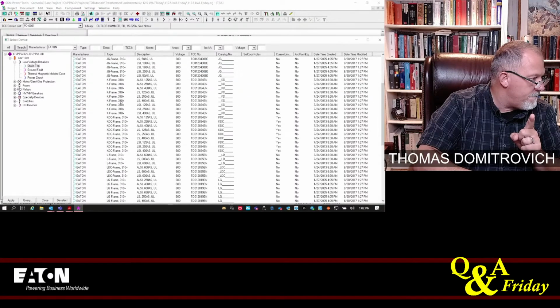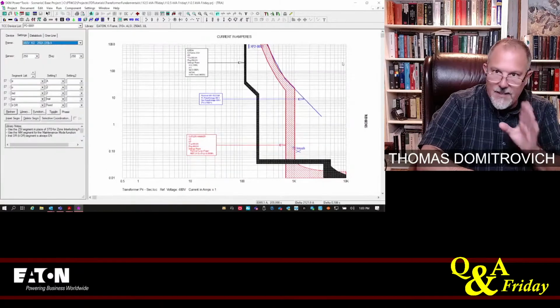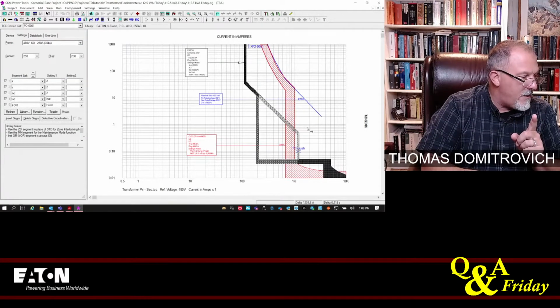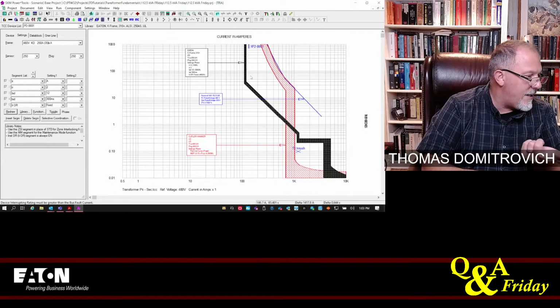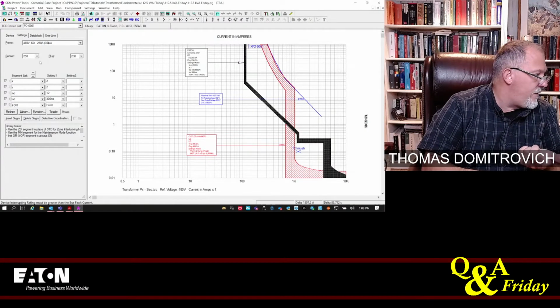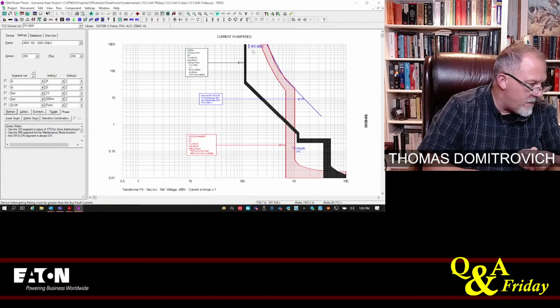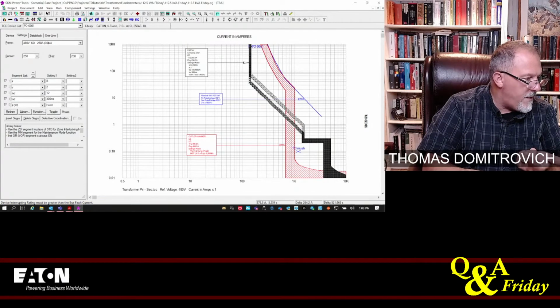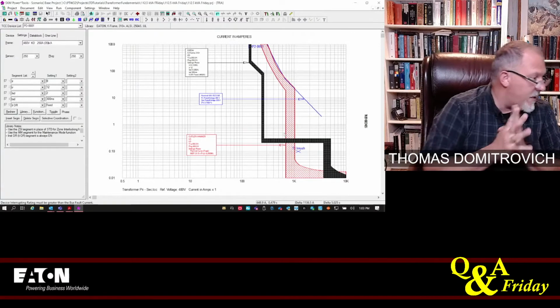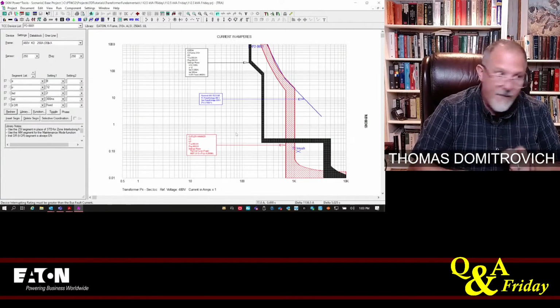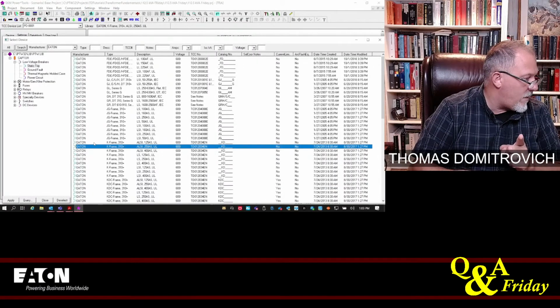I'm going to try a K-frame. Try a K-frame breaker. See, this is the difference between a molded case and, ooh, there we go. Look, I can actually do that. That's 250, but well, let's see, 150 is where? 150 is about right here. There we go. So 150, and add a delay. Bring that down. See, I can do it with an electronic trip unit, but now that is a 250 amp frame instead of a 150 amp frame. That's going to be more expensive. Let's go back to a thermomagnetic.